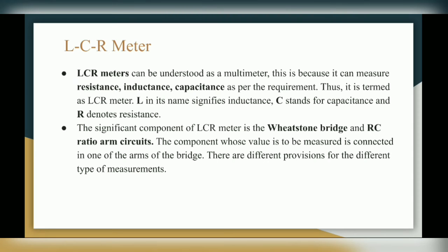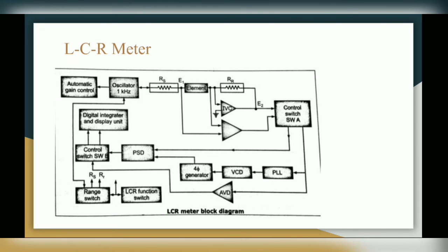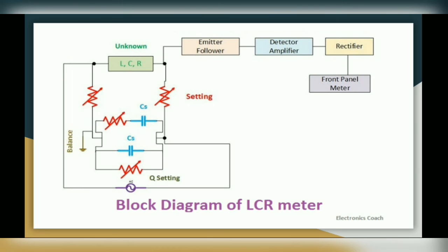The significant component of LCR meter is the Wheatstone bridge and RC ratio arm circuits. The component whose value is to be measured is connected in one of the arms of the bridge. There are different provisions for the different type of measurements. So this is the block diagram of LCR meter. This is another diagram of LCR meter.